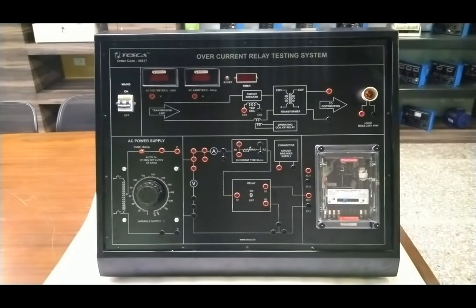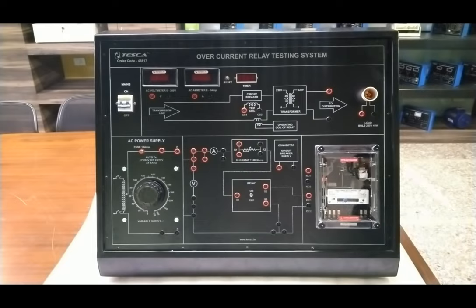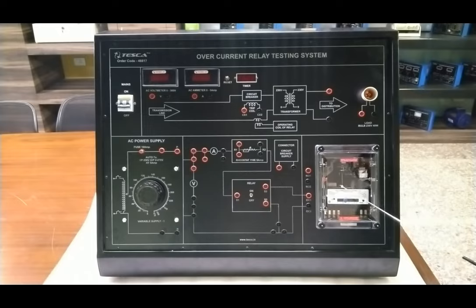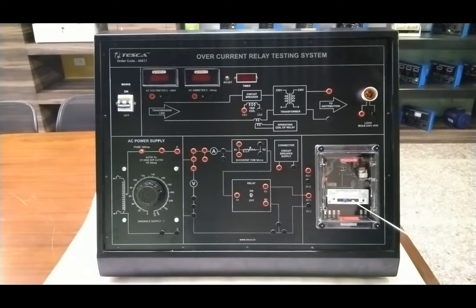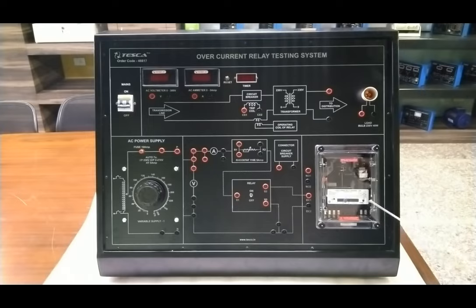The current setting of the overcurrent relay can be done using a plug provided inside the current setting. We will unscrew all the bolts of this mechanical type overcurrent relay, in which the disc plate is provided. When the relay is picking up current more than the current setting value it will start rotating — we will observe this as well. According to the current and time setting, we will set the plug at any value from 0.5 to 2 amperes of the rating.